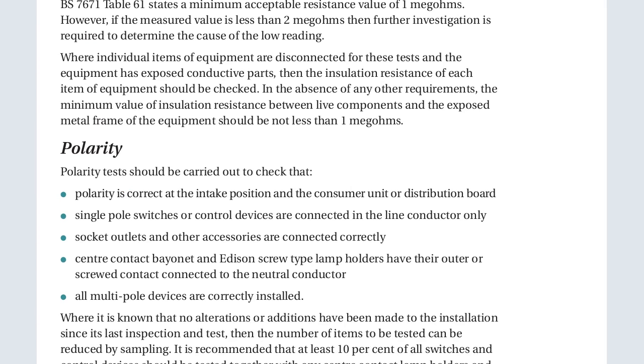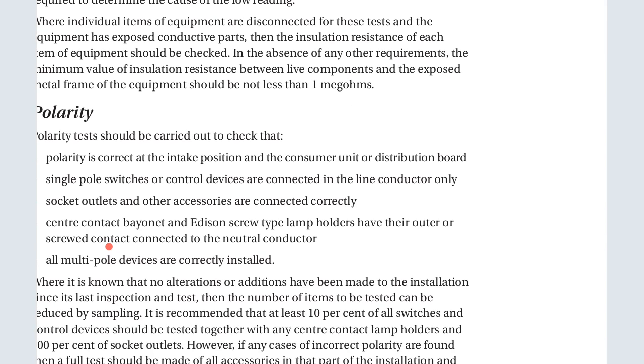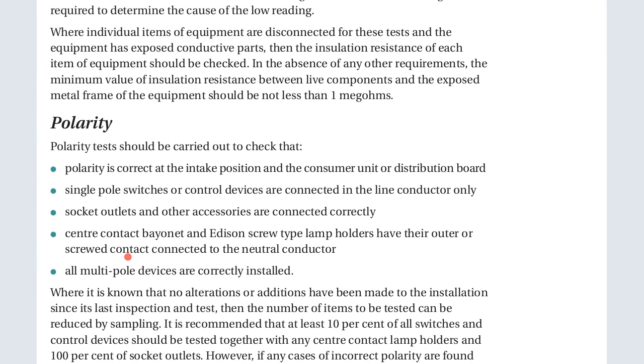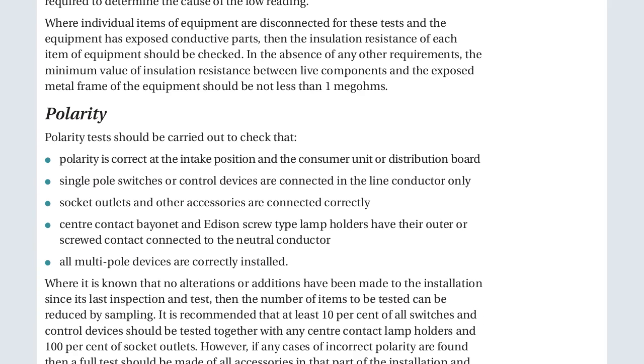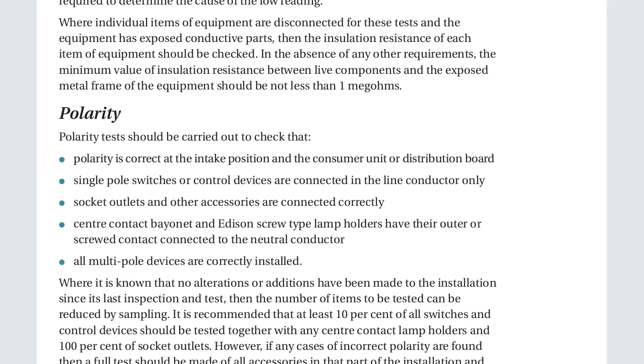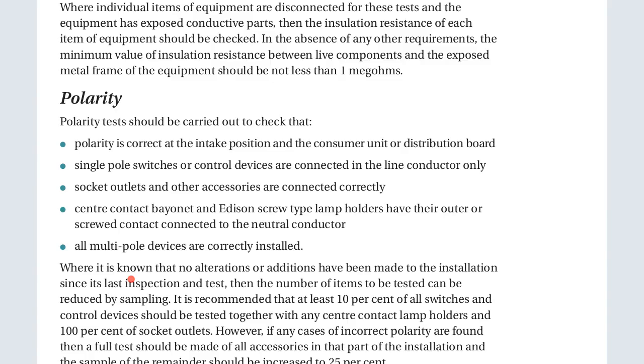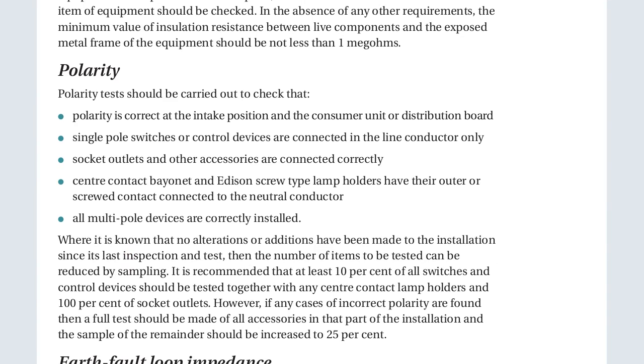Polarity test. The polarity test should be carried out to check that the polarity is correct at the intake position and the consumer unit or distribution board, that single pole switches or control devices are connected in the line conductor only, that socket outlets and other accessories are connected correctly, and that the center contact of the bayonet and Edison screw type holders have their outlet or screwed contact connected to the neutral. That is the polarity. We make sure of the correct intake position of the consumer unit and distribution board, and that the single pole switches and control devices are on the line conductor. In short, we make sure that the live goes to the live and the neutral goes to the neutral.